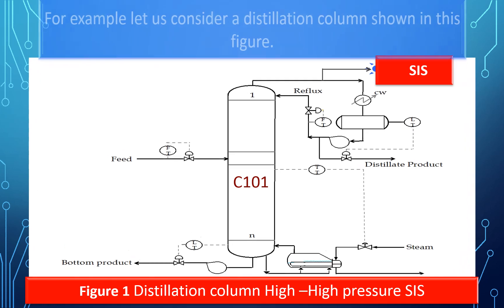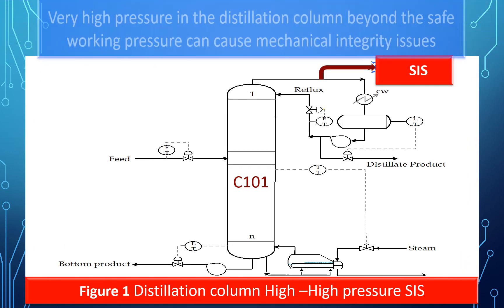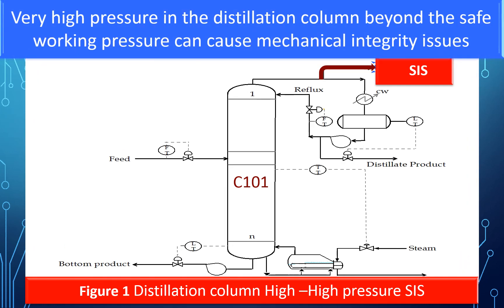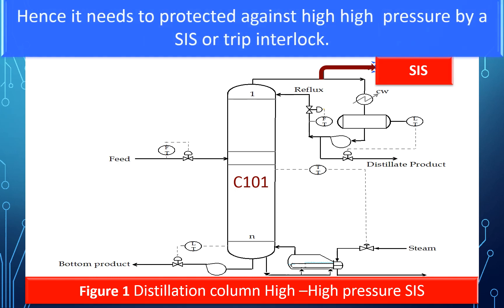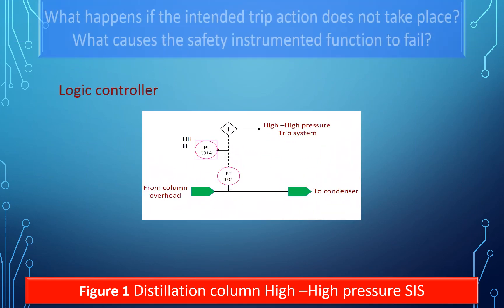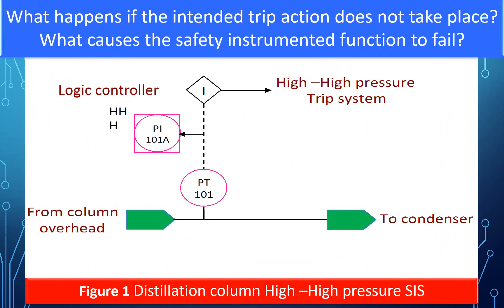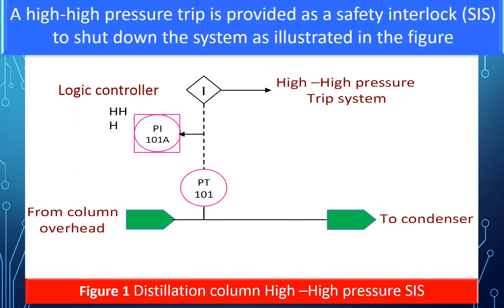For example, consider a distillation column. Very high pressure in the distillation column beyond the safe working pressure can cause mechanical integrity issues and has the potential to cause loss of containment. High pressure can be caused by loss of cooling water, loss of utility, or control valve failure. Hence it needs to be protected against high-high pressure by a SIS or TRIP interlock. A high-high pressure TRIP is provided as a safety interlock to shut down the system. What happens if the intended TRIP action does not take place? What causes the safety instrumented function to fail?